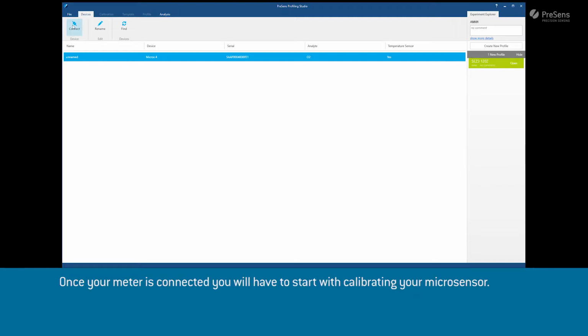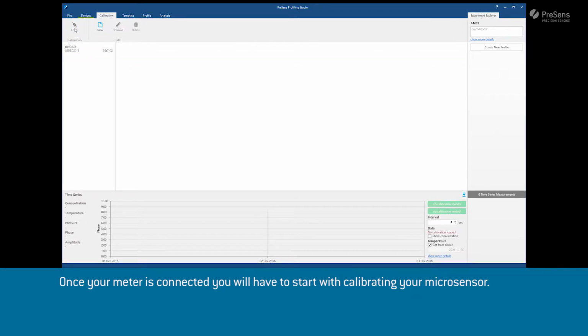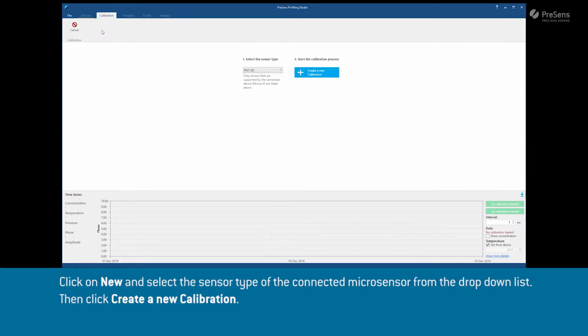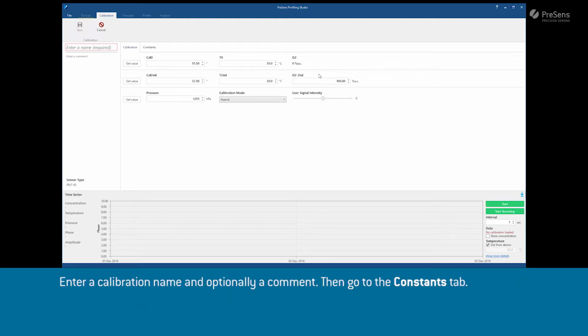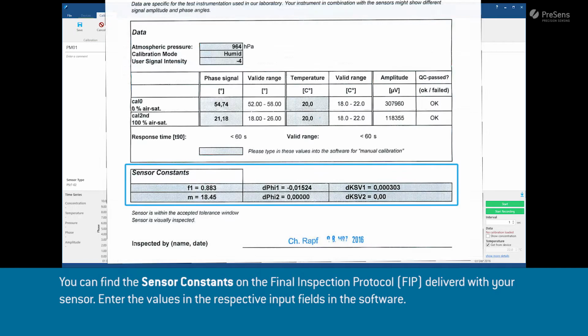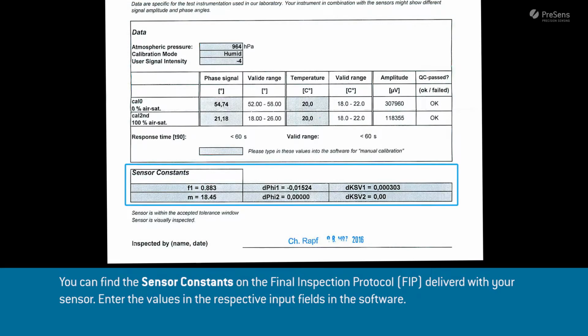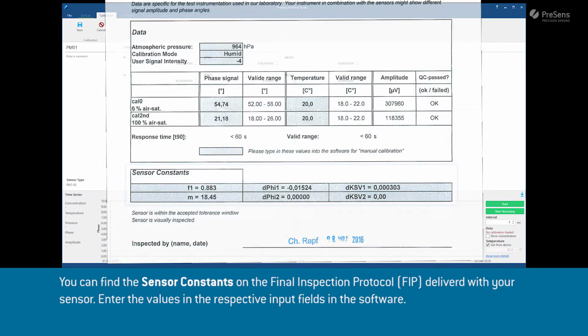Once your meter is connected, you will have to start with calibrating your microsensor. Click on New and select the sensor type of the connected microsensor from the drop-down list. Then click Create a new calibration. Enter a calibration name and optionally a comment. Then go to the Constants tab. You can find the sensor constants on the final inspection protocol delivered with your sensor. Enter the values in the respective input fields in the software.